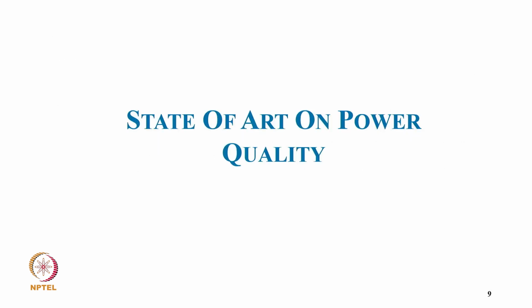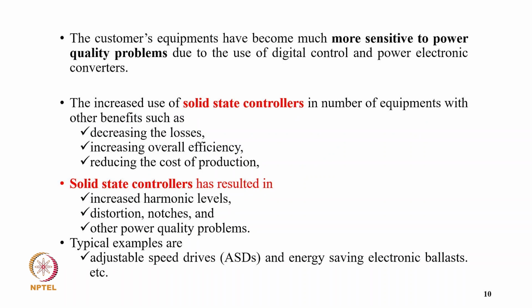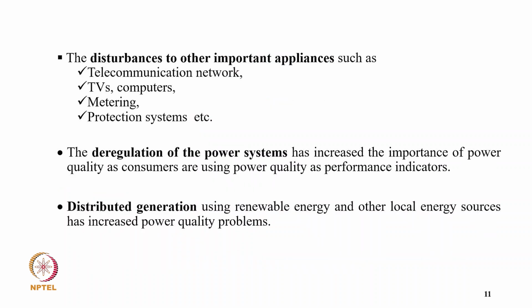Coming to the state of the art on power quality, customer equipment has become much more sensitive to power quality problems due to the use of digital control and power electronics converters and the increased use of solid state controllers in a number of equipment, with other benefits such as decreasing losses, increasing overall efficiency and reducing the cost of production. The solid state controllers have resulted in increased harmonic levels, distortion, notches and other power quality problems, and typical examples are adjustable speed drives and energy saving electronic ballasts, etc. and disturbances to other important appliances such as television networks, telecommunication networks, computers, metering, protection systems, etc.